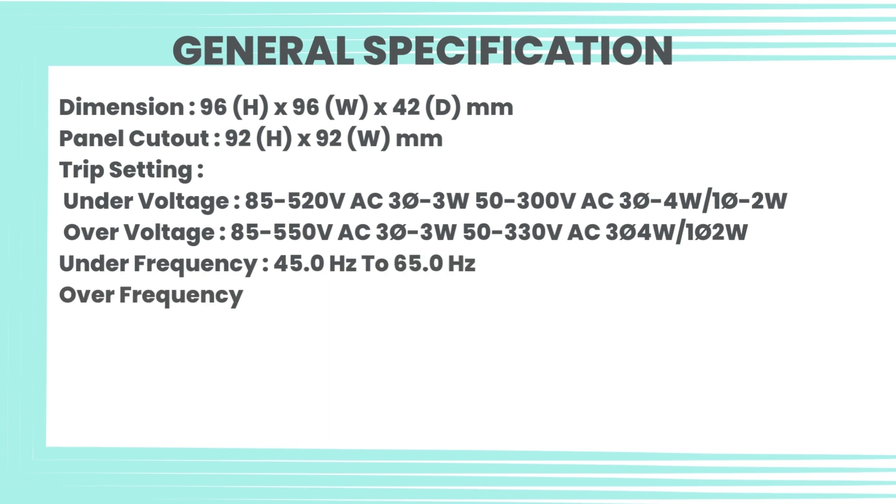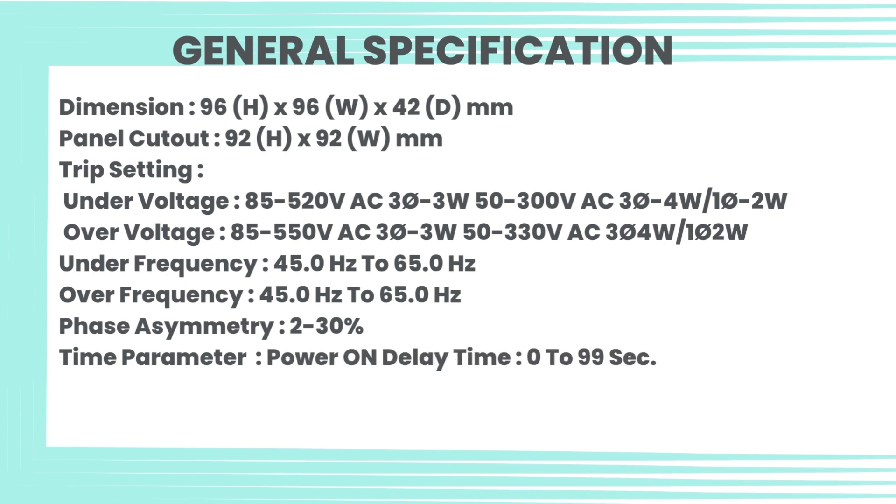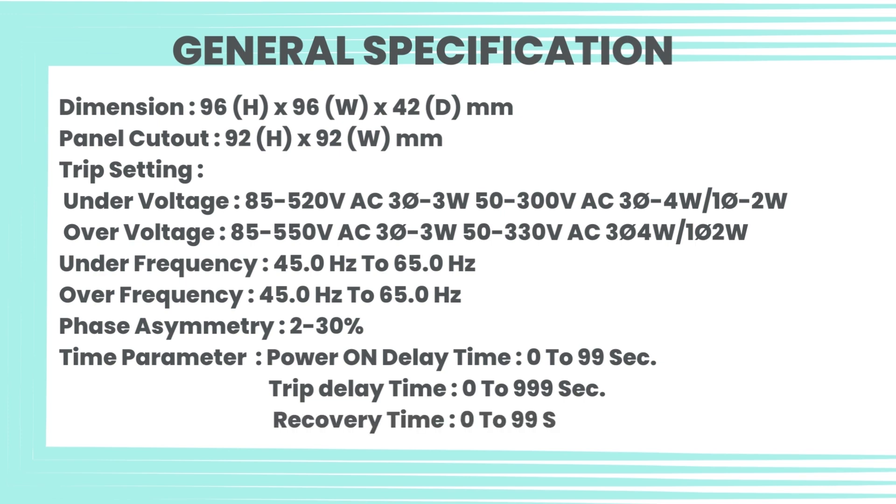Trip settings — Under voltage: 85–520V AC 3Ø-3W, 50–300V AC 3Ø-4W/1Ø-2W. Over voltage: 85–550V AC 3Ø-3W, 50–330V AC 3Ø-4W/1Ø-2W. Under frequency: 45.0 Hz to 65.0 Hz. Over frequency: 45.0 Hz to 65.0 Hz. Phase asymmetry: 2 to 30%. Time parameters: power-on delay 0–99 seconds, trip delay 0–999 seconds, recovery time 0–99 seconds.